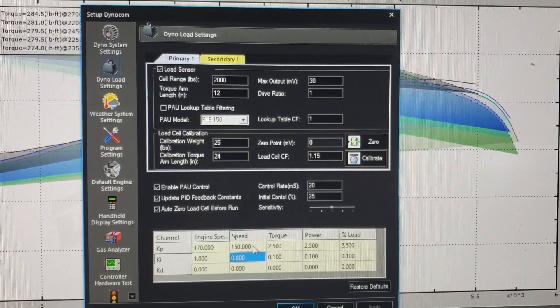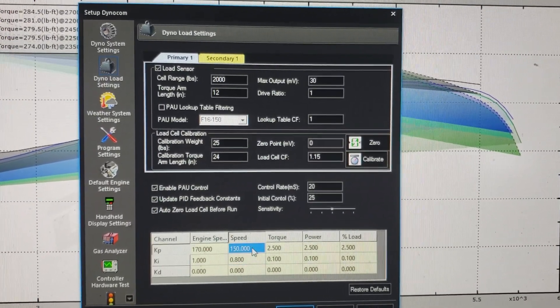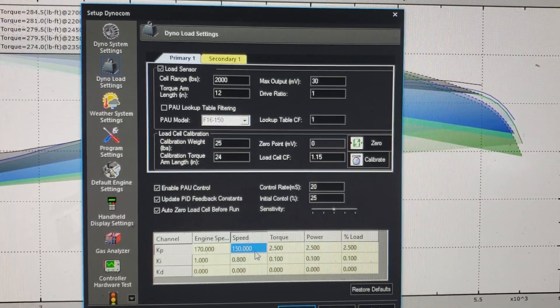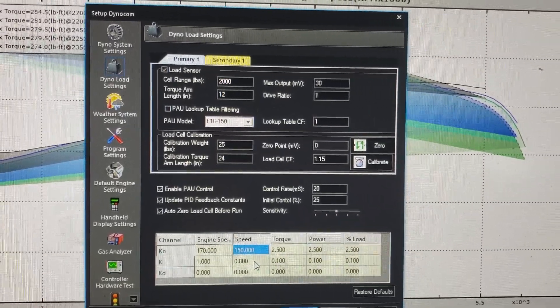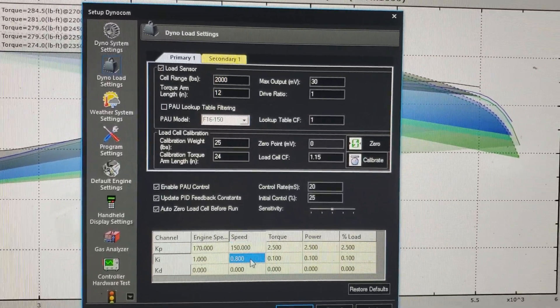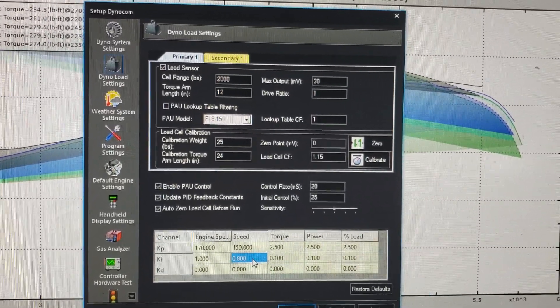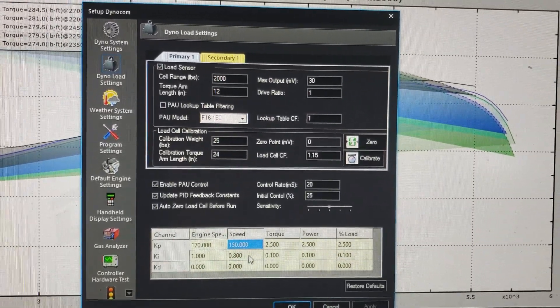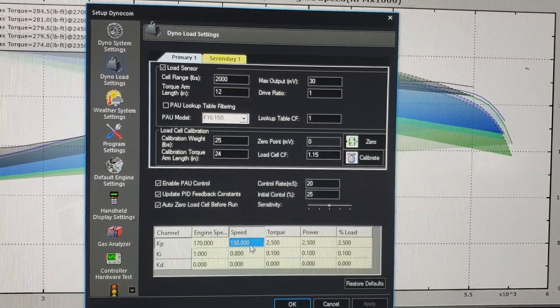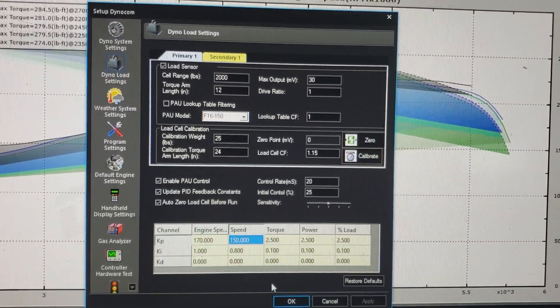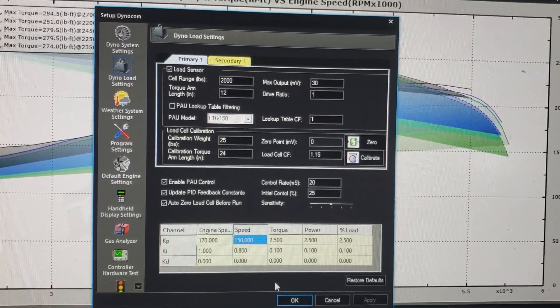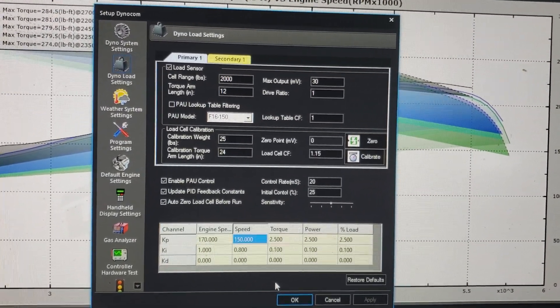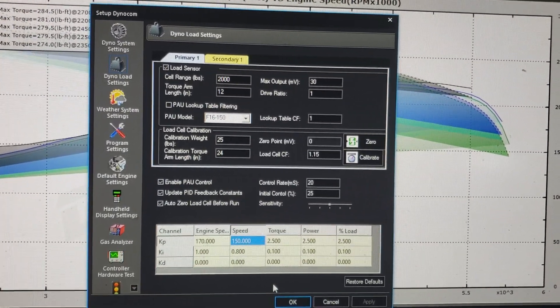If it comes on too strong, lower the P. If you'd like the stabilization time to increase, increase I. But start with the default settings first. For newer systems it's already pre-configured, so you shouldn't have to touch any of this. That's it. Bye-bye.